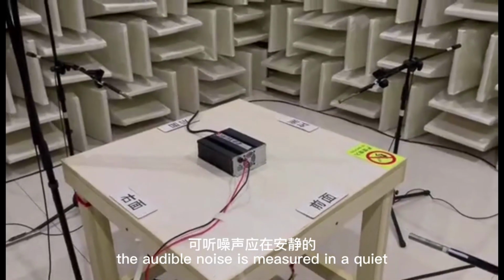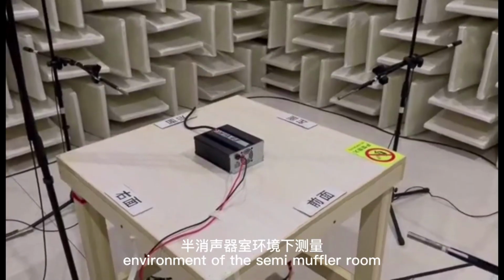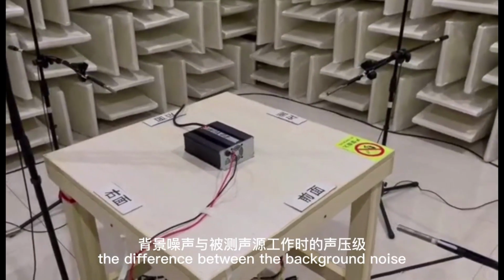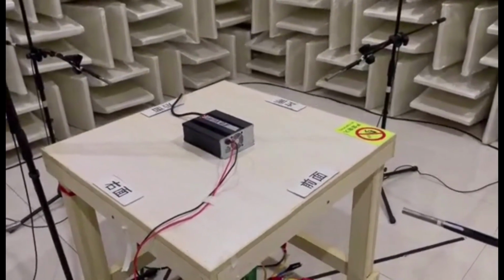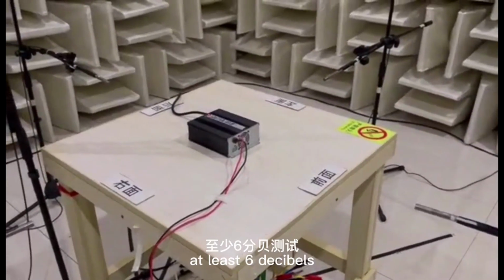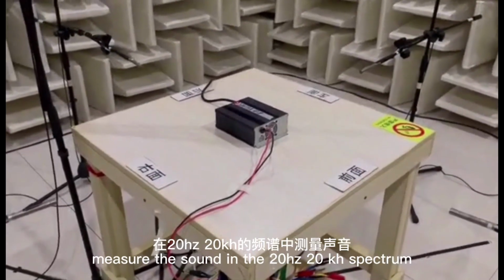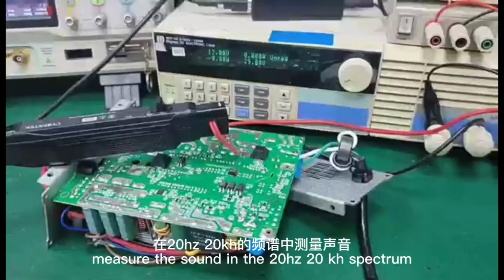The audible noise is measured in a quiet environment of the semi-anechoic room. The difference between the background noise and the measured sound source should be at least 6 decibels. Measure the sound in the 20 Hz to 20 kHz spectrum.